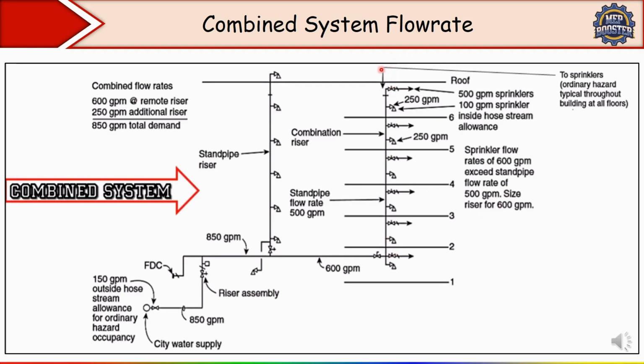So 600 GPM means the sprinkler flow rate is coming more than standpipe, so we need to consider the sprinkler flow rate 600, and for additional standpipe 250, you know that. So 600 plus 250, 850 GPM, this is our combined flow rate demand. In this way you need to calculate. It is very simple, okay.